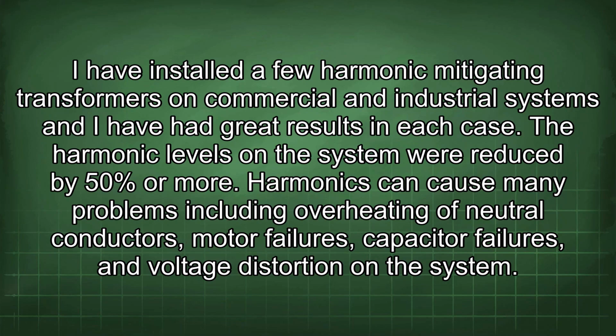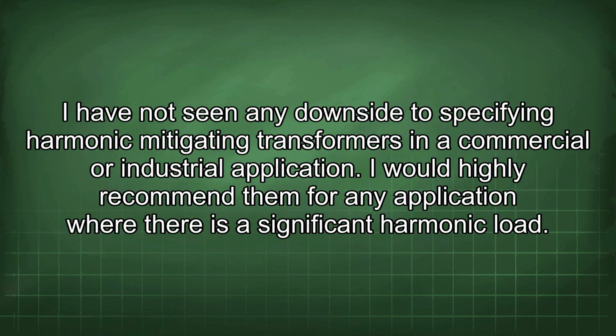I have installed a few harmonic mitigating transformers on commercial and industrial systems, and I have had great results in each case. The harmonic levels on the system were reduced by 50% or more. Harmonics can cause many problems, including overheating of neutral conductors, motor failures, capacitor failures, and voltage distortion on the system. I have not seen any downside to specifying harmonic mitigating transformers in a commercial or industrial application.